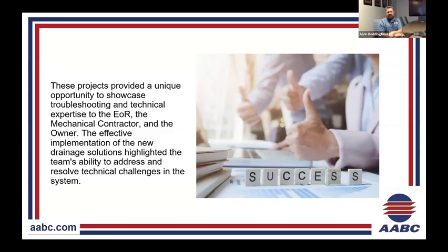There's one thing after the next, and I think it provided a unique opportunity. It was a good learning experience for my guys, and it gave us some lessons learned, to the point where just because the submittal shows it, there might be a miscommunication somewhere. And then trying to troubleshoot the bags that would constantly float up into the basin. One time you'd run that chiller for 30 minutes and have no issues, and then another time it'd be 5 minutes and suddenly the bags would cling.